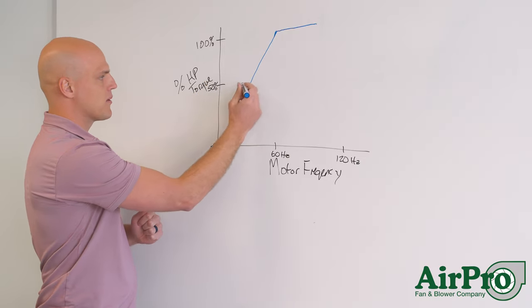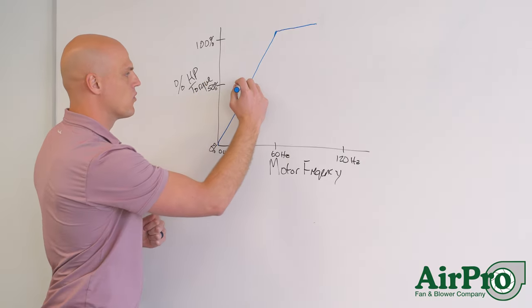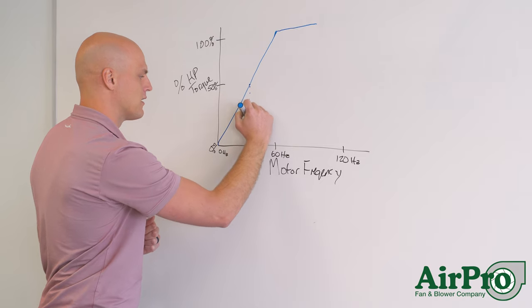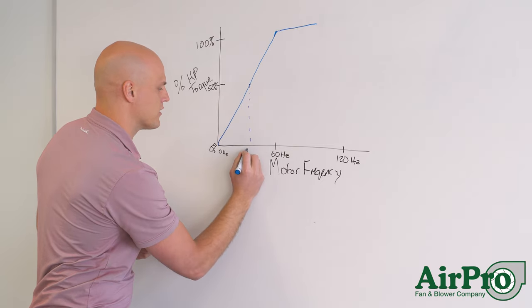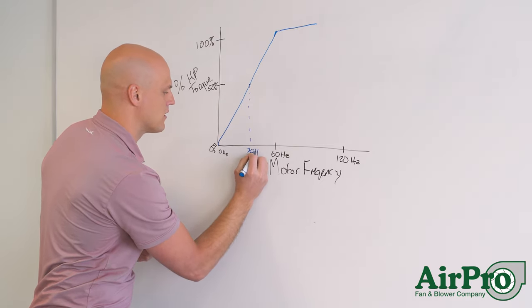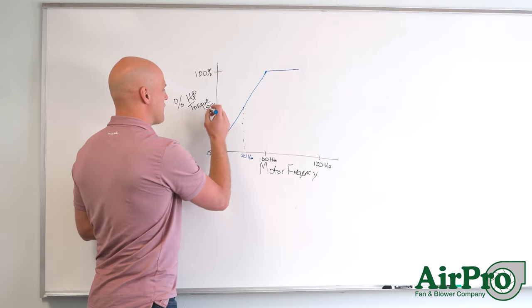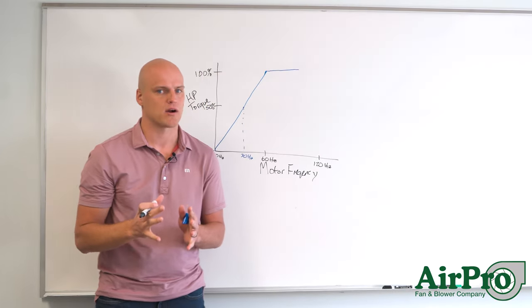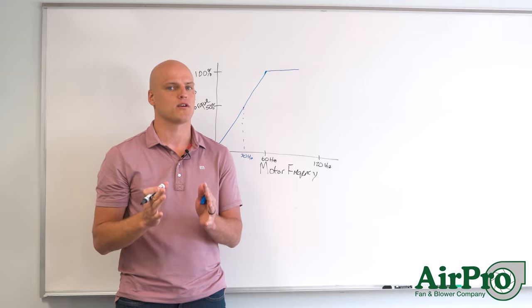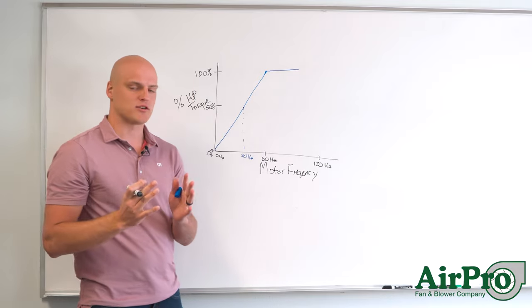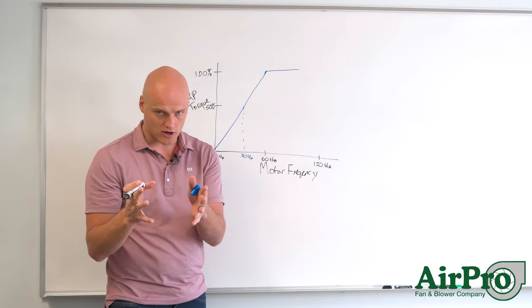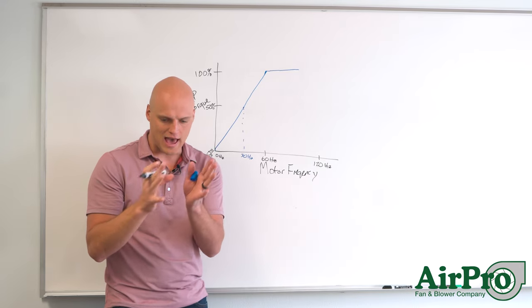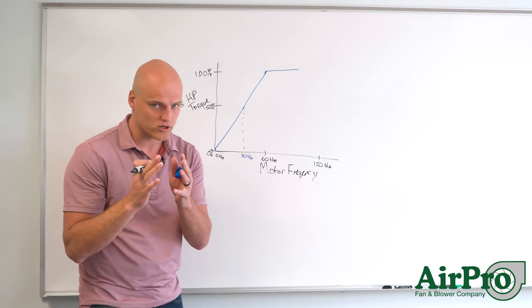So at this 50 percent mark right here we're running at 30 hertz. And we have 50 percent of the motor horsepower available. This is really important to understand. Because if you're taking an 1800 rpm motor and at 1800 rpm you have 100 horsepower available.